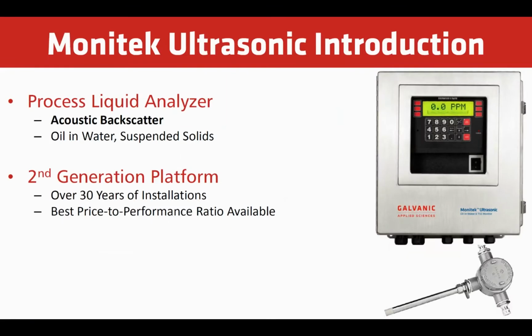Monitek Ultrasonic is a two-part system similar to our optical, where we use the AT3 ultrasonic transmitter connected to the ultrasonic AS3 sensor via cables. It works on acoustic backscatter, which means we send out an acoustic pulse and we listen to the echo return proportional to the higher or lower ppm values. We typically use these to do oil in water measurements in high-level suspended solids where an optical device would fail because of window coatings or too dark of a sample to allow the light through.